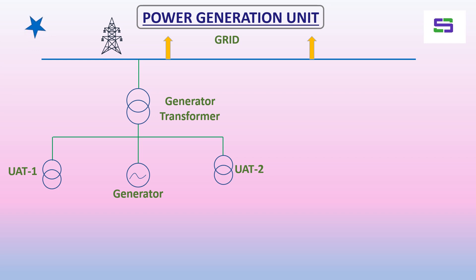This power will be tapped from the generator terminal itself. The connection between the generator and the generator transformer has a common tapping point, and generally this is an IPB — Isolated Phase Bus. So the power supply is tapped from there on the HV side of the UAT, and it will be stepped down.